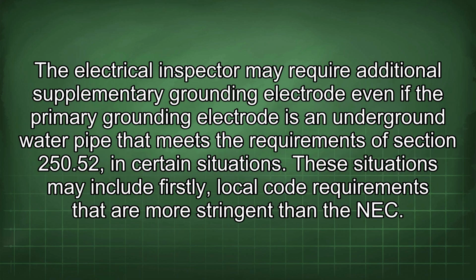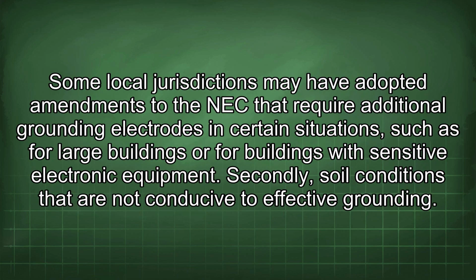The electrical inspector may require an additional supplementary grounding electrode even if the primary grounding electrode is an underground water pipe that meets the requirements of section 250.52 in certain situations. These situations may include, firstly, local code requirements that are more stringent than the NEC. Some local jurisdictions may have adopted amendments to the NEC that require additional grounding electrodes in certain situations, such as for large buildings or for buildings with sensitive electronic equipment.